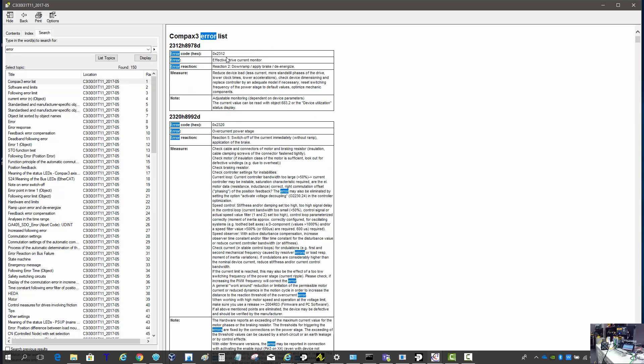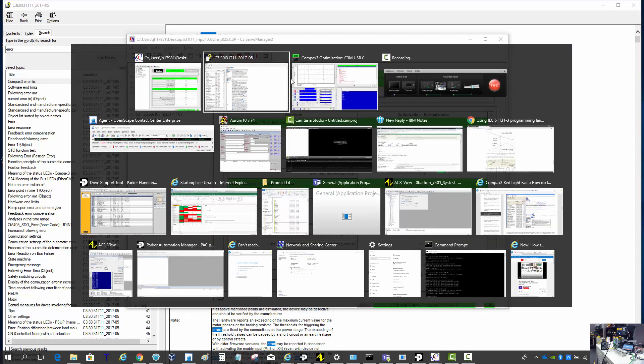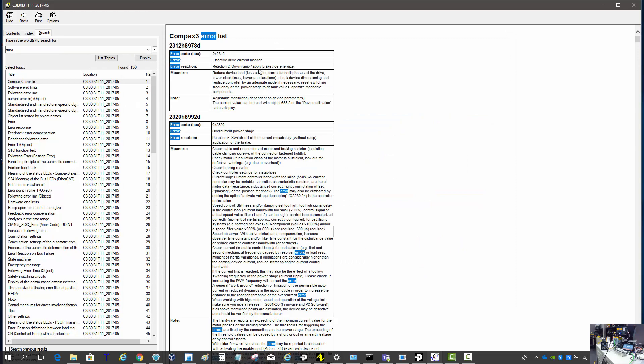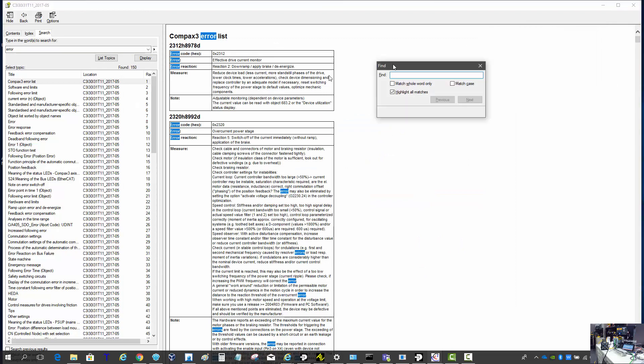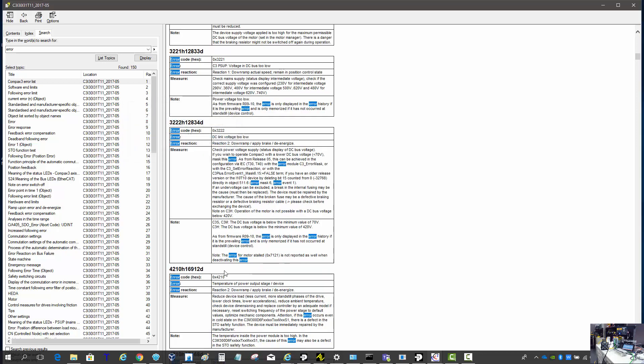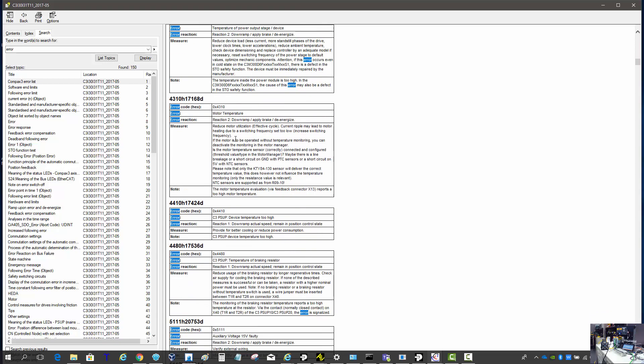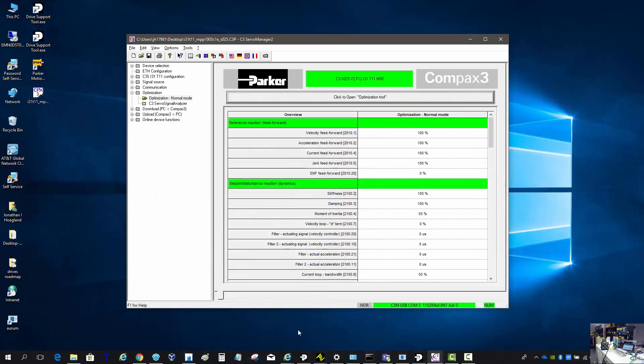The error list shows you the hex number and the decimal number of that same hex code. In the optimization screen, it shows you the hex number. So let's say 4310 as an example — you can do a Control+F on that page, type 4310, and it jumps you down and gives you the symptom, cause, and remedy of what caused that error. That's how to look up more details on the error.